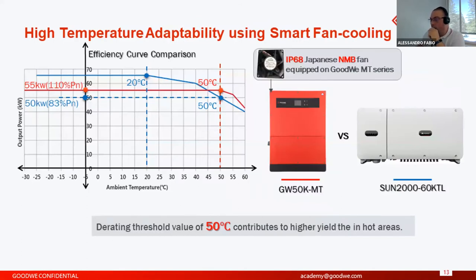Another really important point is the high temperature adaptability, because we have a cooling system inside, also with fans, and we can increase our efficiency with a derating threshold value of 50 degrees. So this is also a very important thing. Also for the MT series, for the 50 kilowatt models, we have 55 kilowatt input, and also the derating starting at 50 degrees, compared to some other competitors, for example.